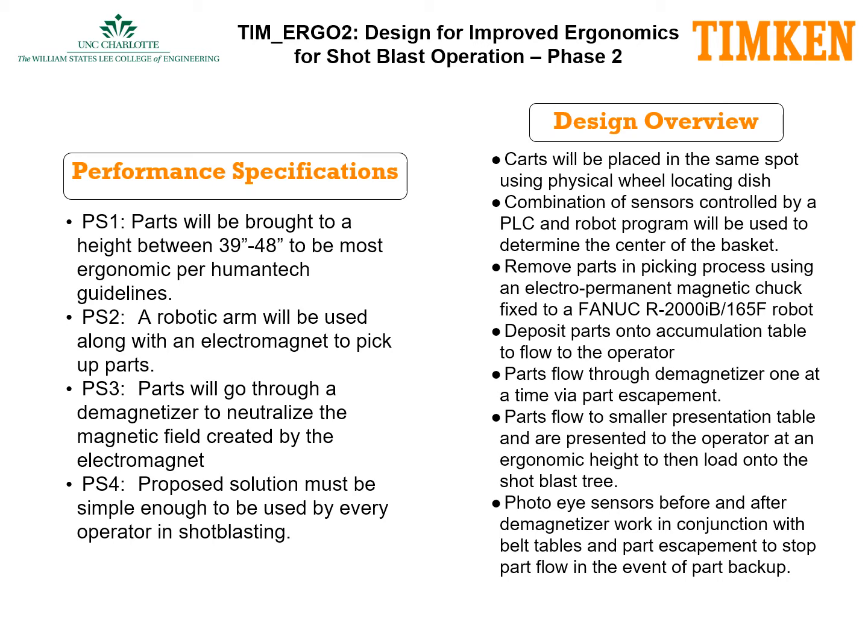The design overview for Temergo 2 follows. Parts will be placed in the same spot using physical wheel locating dish. A combination of sensors controlled by a PLC and robot program will be used to determine the center of the basket. Removal of parts in a picking process will use an electropermanent magnetic chuck fixed to a FANUC R-2000iB/165F robot. The robot deposits the parts onto an accumulation table to flow towards the operator.